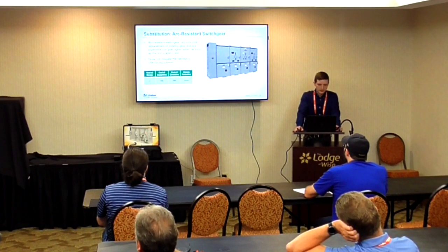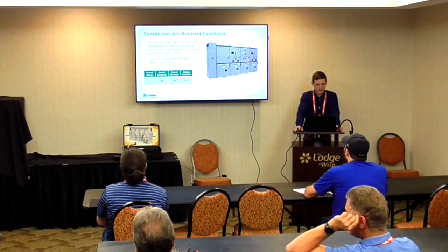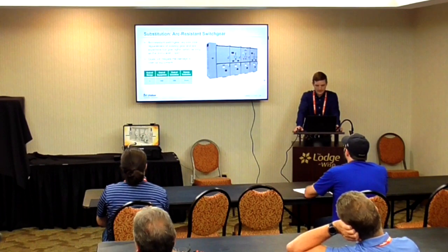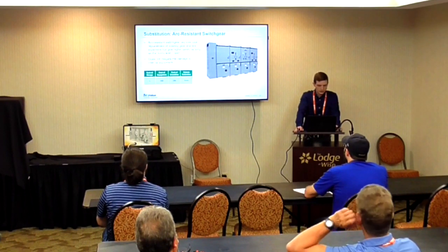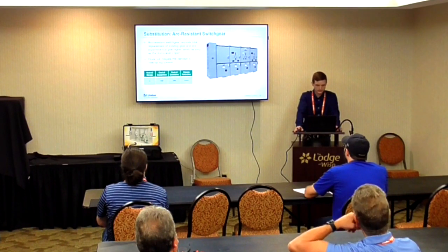Problem with this is if the door is open and somebody is working on it, then it's not going to do anything for you. It's still going to be directed at the nearest enclosure, and that is not going to really help. Also important to note here that this is not an approved method for NEC 240.87. You will still see this used a lot in the field as just an additional method to a lot of other things, but it is not an approved method by itself.